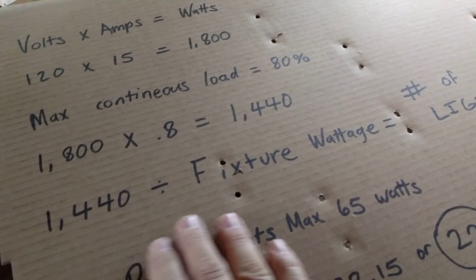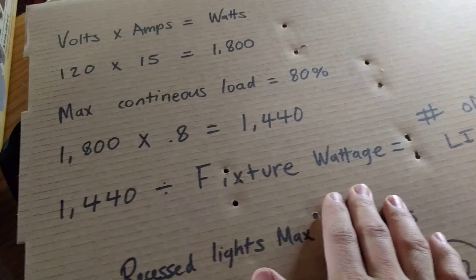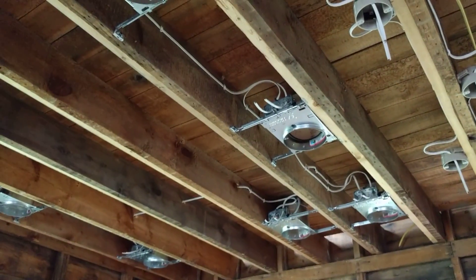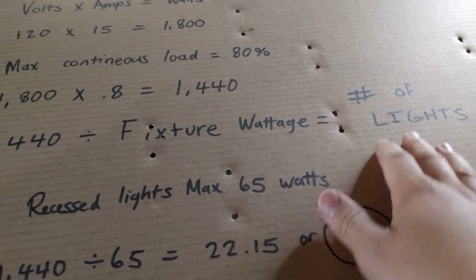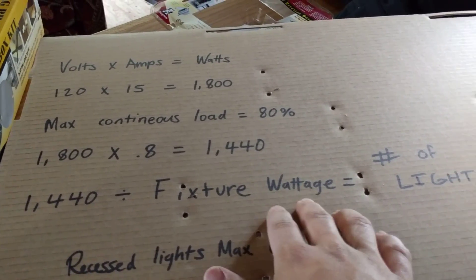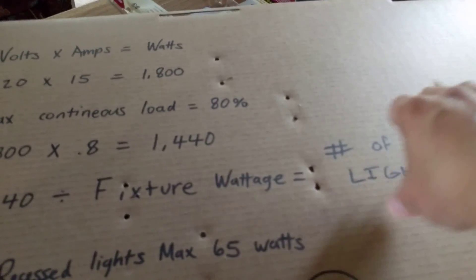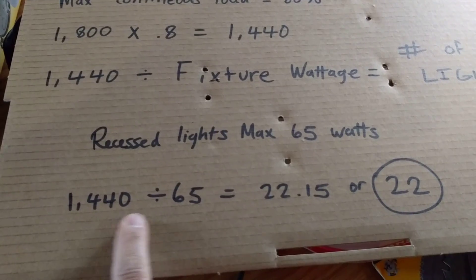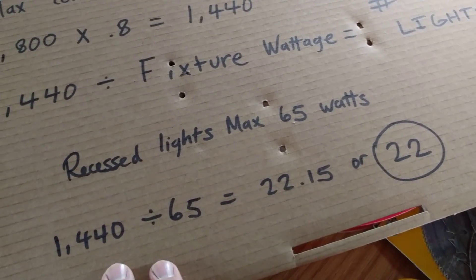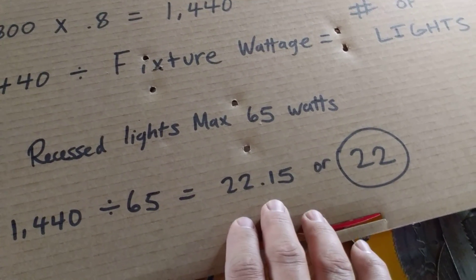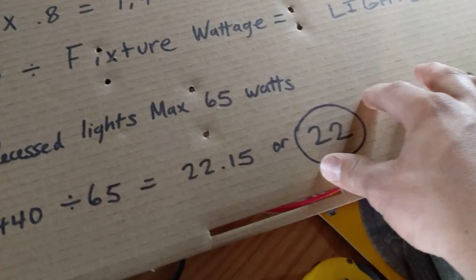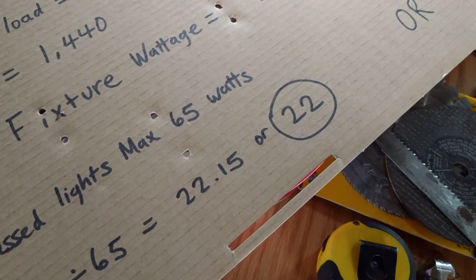So now we take our 1440 divided by our fixture wattage. Your typical recessed light incandescent bulb is usually 65 watts. You divide 1440 by your fixture wattage and that gives you your number of light fixtures. So: 1440 divided by 65 equals 22.15 fixtures, or 22 rounding down. So with that simple calculation, assuming you're going to be using incandescent, you would put 22 recessed lights on a circuit.